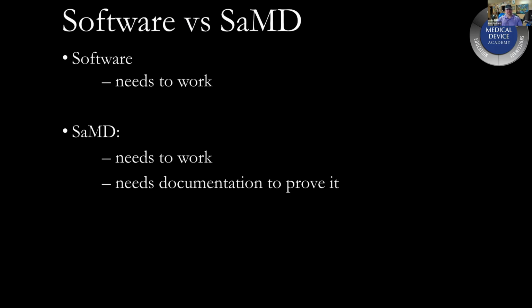The software you iterate multiple times, we keep improving it, we have a minimum viable product, and we finally have a final version we deliver to the customer. Same thing for the documentation. You can iterate many, many times and deliver those pieces as you go and edit them. They don't have to be final approved versions until you submit to the FDA, and even the FDA may make you make some changes, like labeling. That's one of the things I try to teach them.